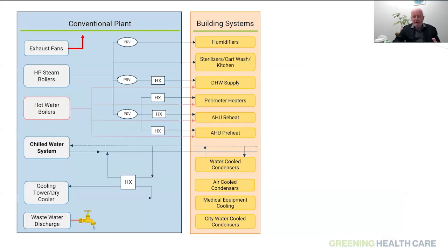We're familiar with conventional plants. We've got exhaust fans that blow away conditioned air, often 24/7, right through the heating season and right through the cooling season. We've got steam boilers, we've got hot water boilers, and sometimes those are working together. What is reality for us in almost every hospital is that the chilled water system becomes the heat transporter. On a year-round basis, it's the way that you'll be collecting heat from different parts of the hospital and moving it to heat recovery chillers, typically, to where it can be used. So the chilled water system takes on an all-year vital role.